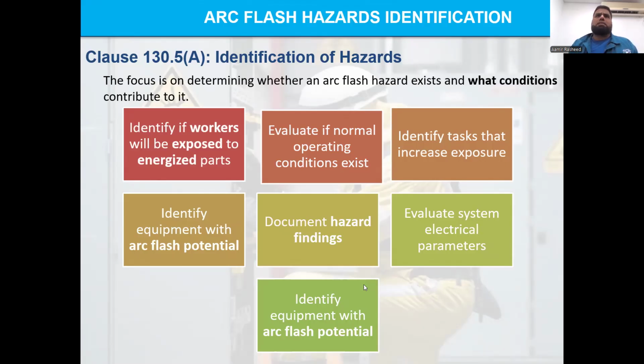When we talk about any kind of hazards or risk, the very first step is the identification of the hazards. So first comes identification of the arc flash hazards.